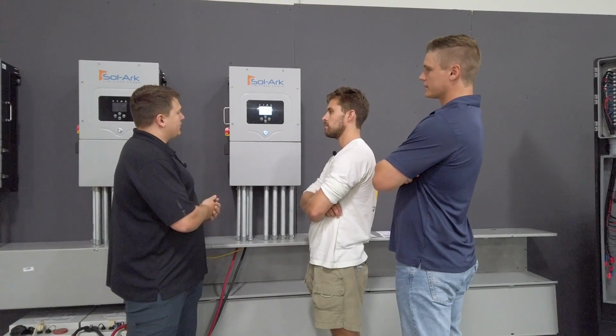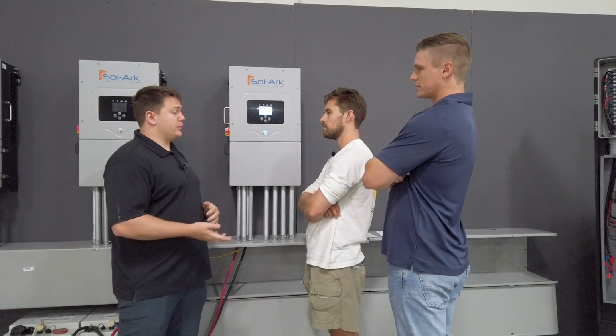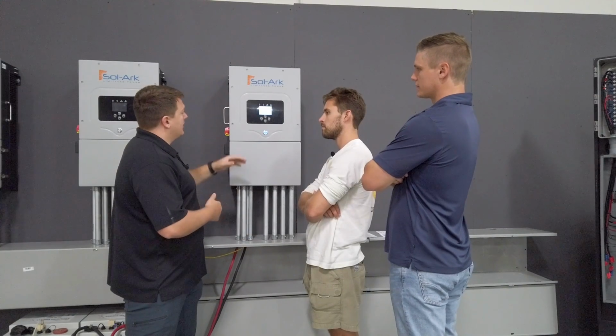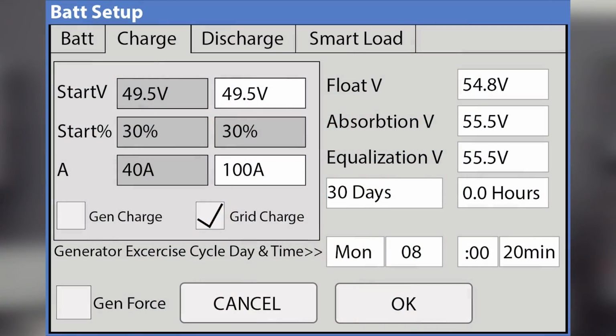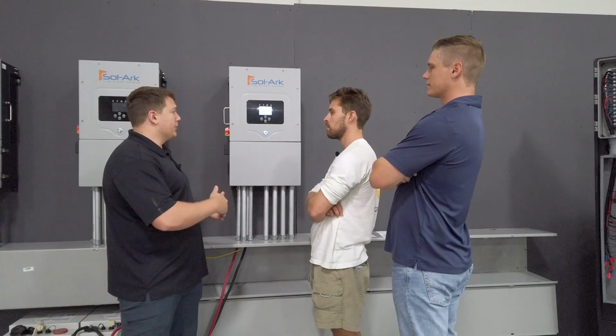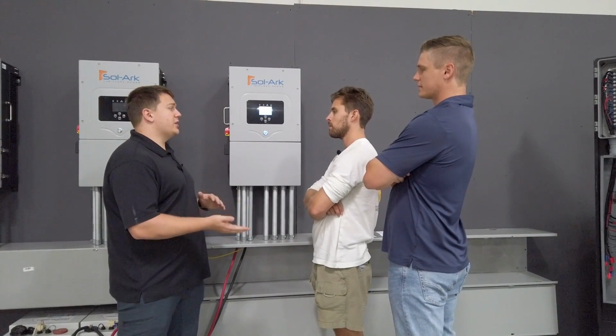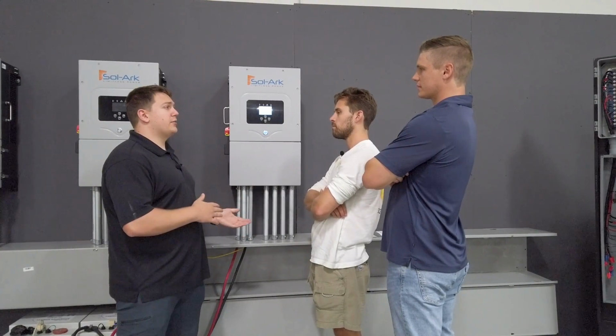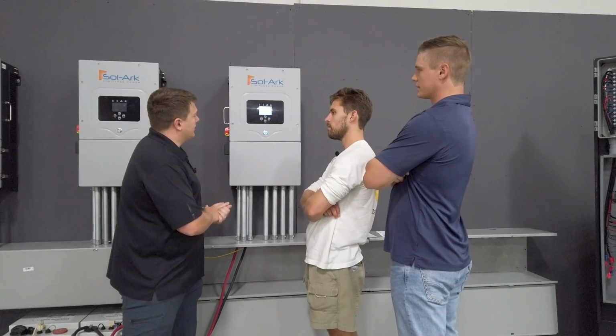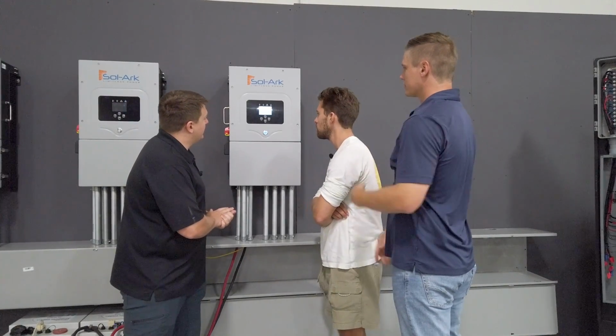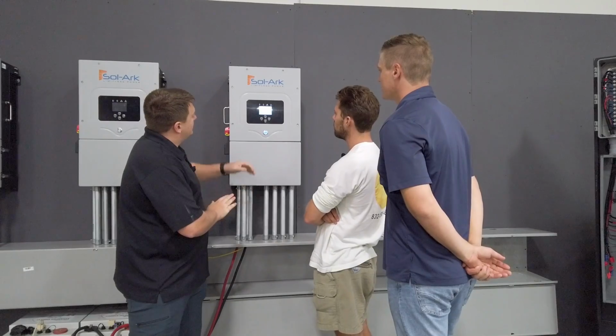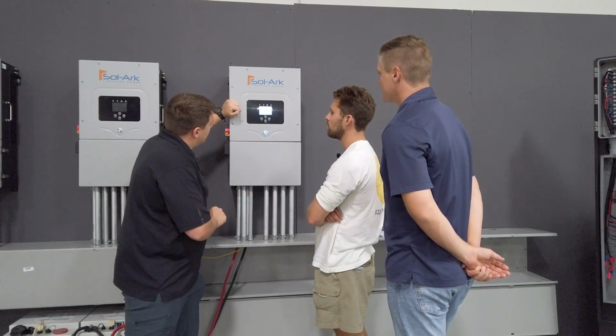So if you have a 2-wire start compatible generator, and you want that to turn on, the default here is set to 49.5 volts. So if the battery gets to 49.5 volts, it'll call for your generator. Now technically it has to be below this for 1 minute, and it does adjust for how many amps you're pulling out of the battery in real time using another setting that we're going to get to in a moment. But anyways, that's what those settings are there.